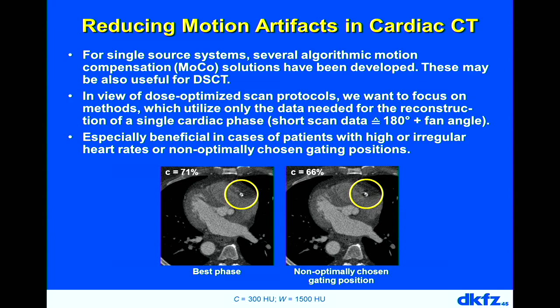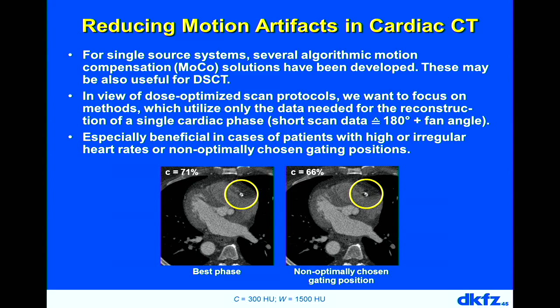A retrospectively gated scan has a best phase — for one patient it was at 71% between R-peaks — showing the least motion artifacts. Moving just a few percentage points away, for example to 66%, already introduces significant motion artifacts. It's critical to find the best phase and acquire X-ray data only in that window, but it's not easy. The example shows a best phase image and the phase 5% away with visible artifacts.